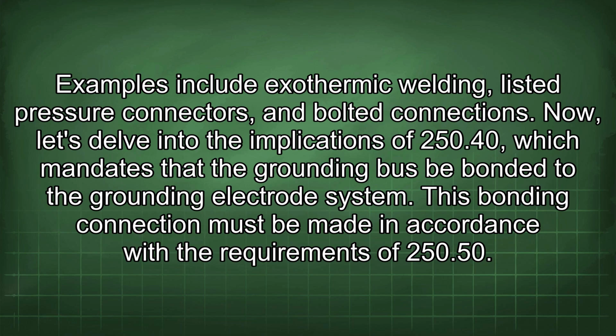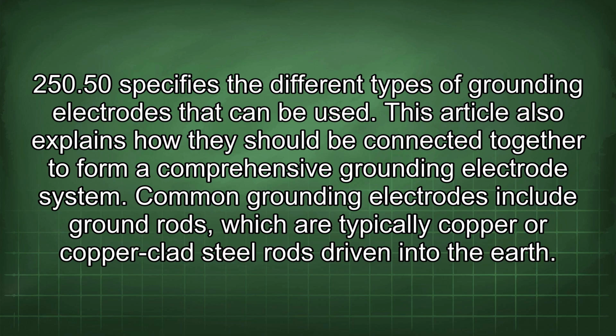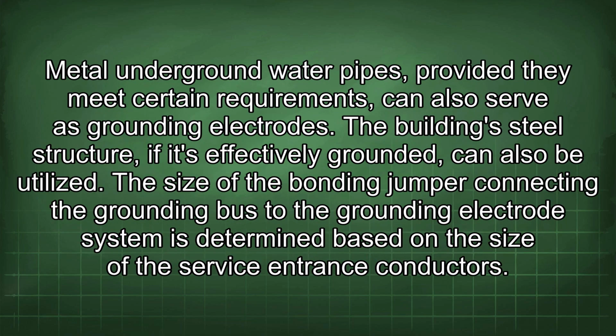Now let's delve into the implications of 250.40, which mandates that the grounding bus be bonded to the grounding electrode system. This bonding connection must be made in accordance with the requirements of 250.50. 250.50 specifies the different types of grounding electrodes that can be used. This article also explains how they should be connected together to form a comprehensive grounding electrode system. Common grounding electrodes include ground rods, which are typically copper or copper-clad steel rods driven into the earth. Metal underground water pipes, provided they meet certain requirements, can also serve as grounding electrodes. The building's steel structure, if it's effectively grounded, can also be utilized.